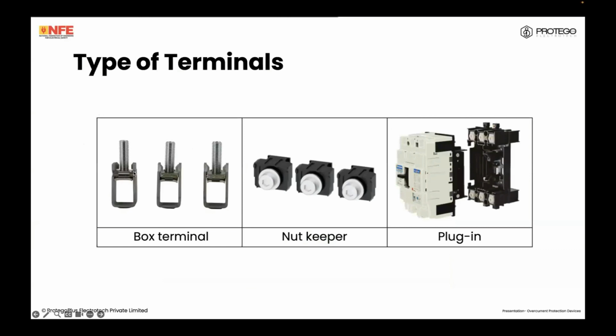When it comes to connecting our circuit breakers and fuses to our wiring system, you have the box terminal. This is what's seen in MCBs. The wire just goes in, there's a screw on top, it clamps down. You have the nut keeper, which is for lugs. The lug goes in, the nut and the nut fastens on.